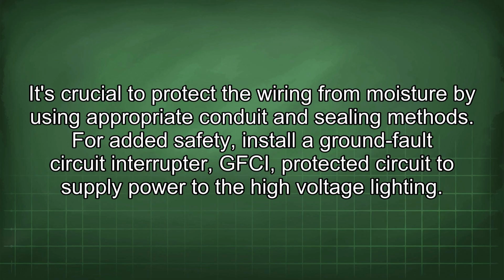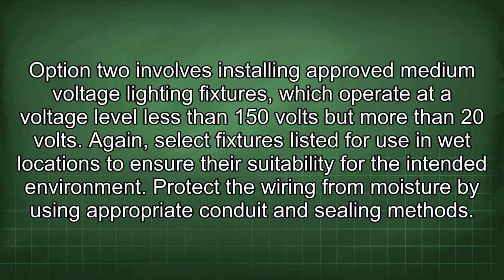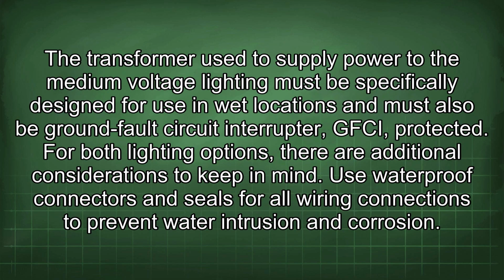For added safety, install a ground fault circuit interrupter, GFCI, protected circuit to supply power to the high voltage lighting. Option 2 involves installing approved medium voltage lighting fixtures, which operate at a voltage level less than 150 volts but more than 20 volts. Again, select fixtures listed for use in wet locations to ensure their suitability for the intended environment. Protect the wiring from moisture by using appropriate conduit and sealing methods. The transformer used to supply power to the medium voltage lighting must be specifically designed for use in wet locations and must also be ground fault circuit interrupter, GFCI, protected.